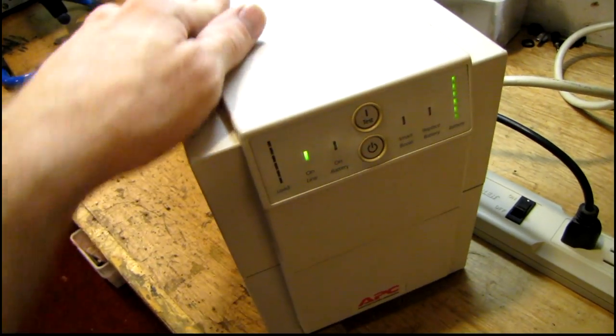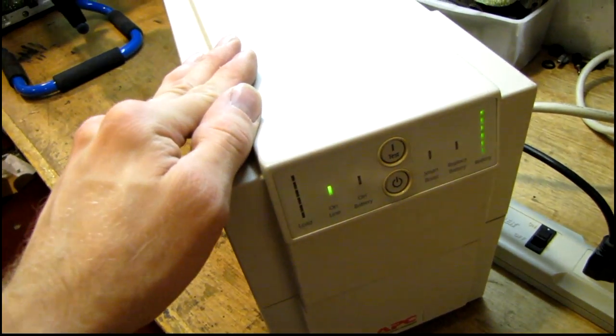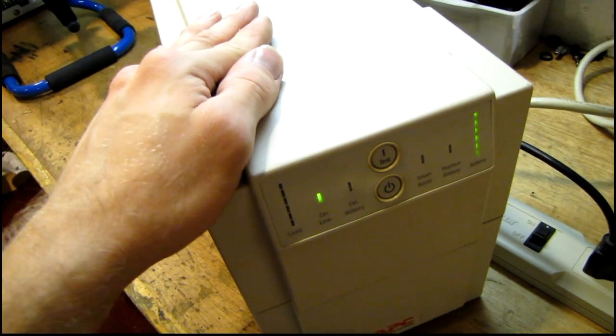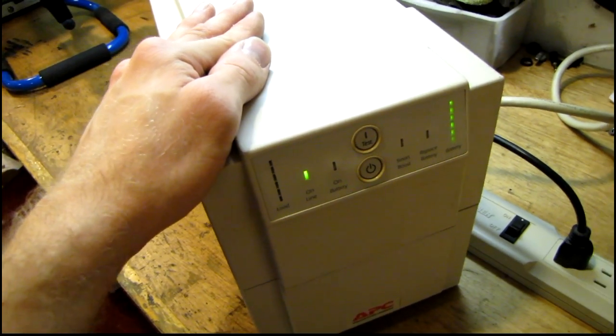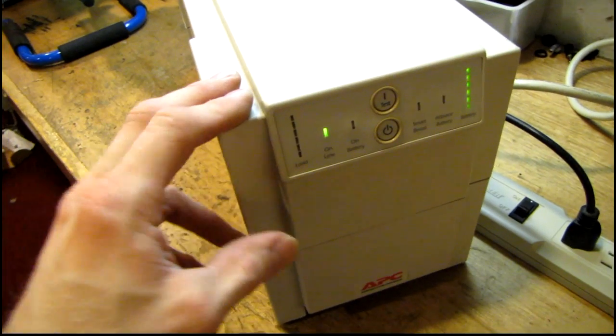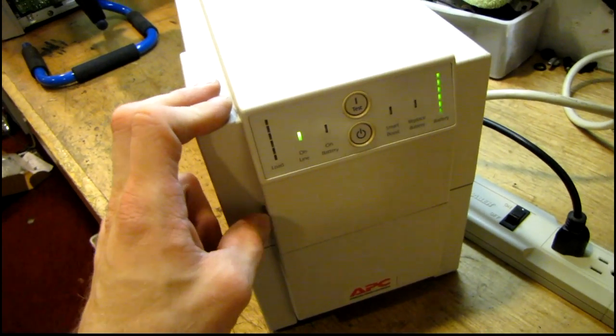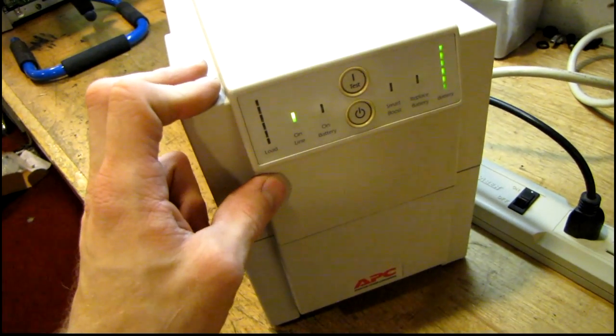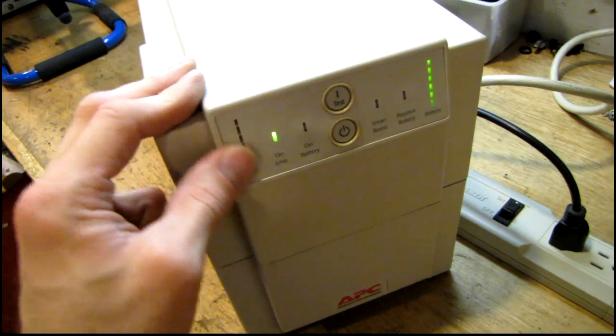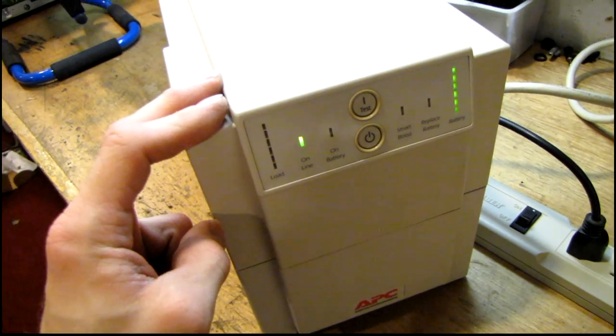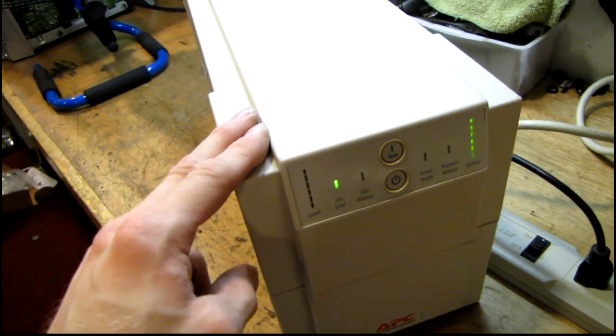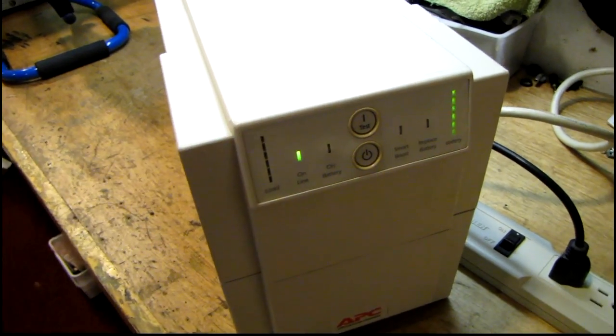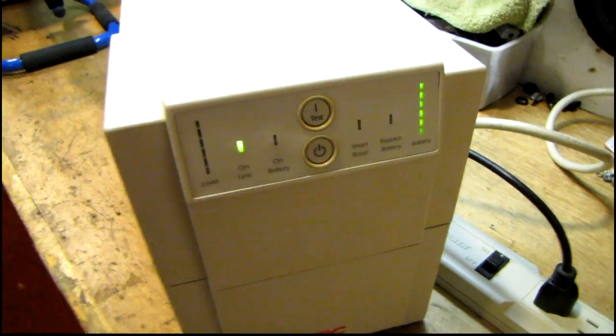What that does is it gives the CPU in the UPS a perfectly stable reference right at the midpoint of the load. And after the batteries are drained and recharged, it knows exactly how long the batteries will last at a given load. If you were to use something like a computer to calibrate the UPS, the load would vary too much while you're using it. And that wouldn't give an accurate reference point for the CPU. So your battery gauge wouldn't be accurate.